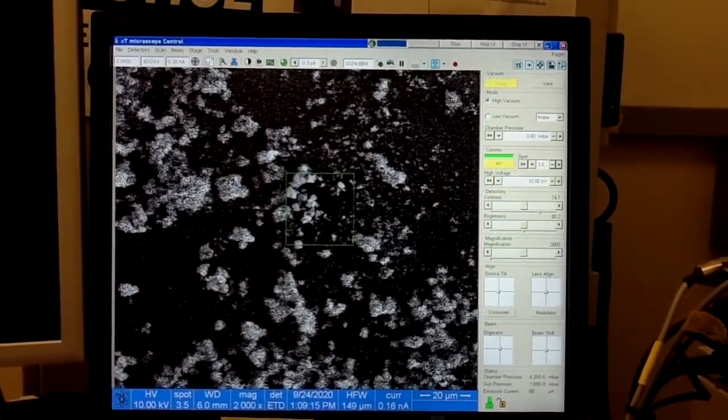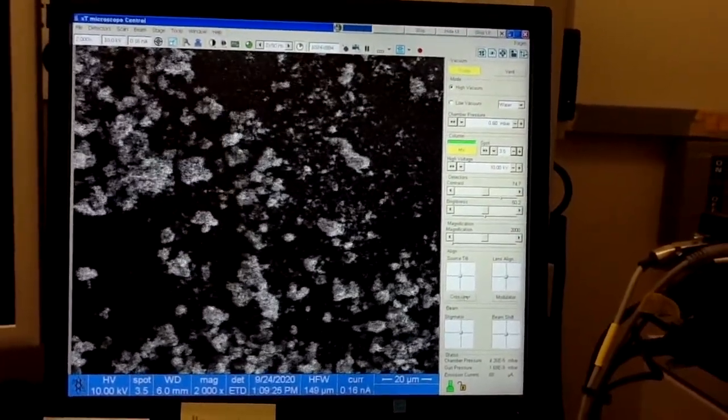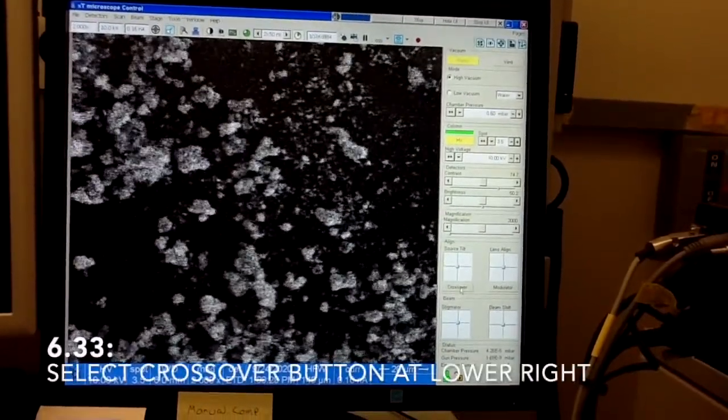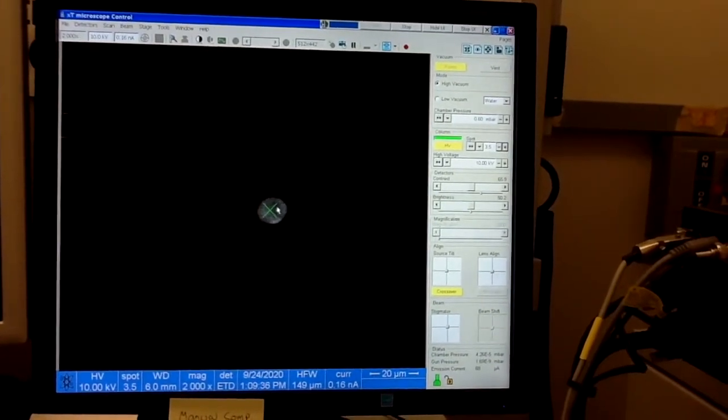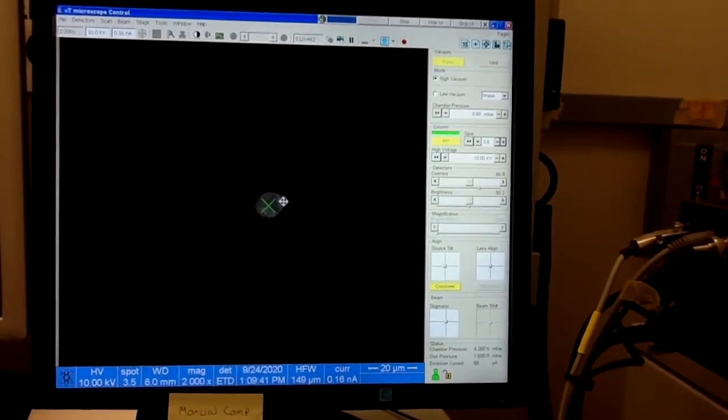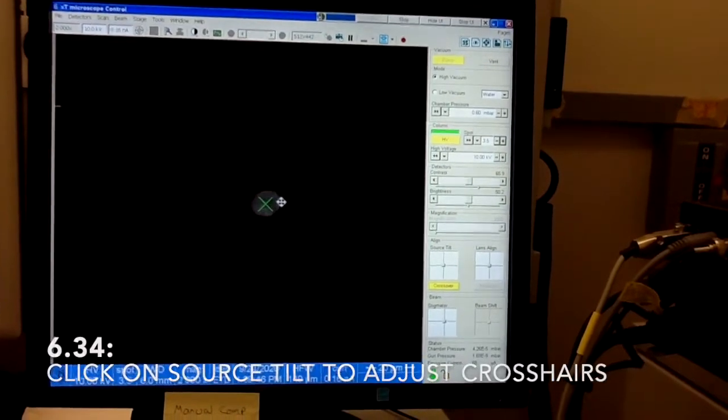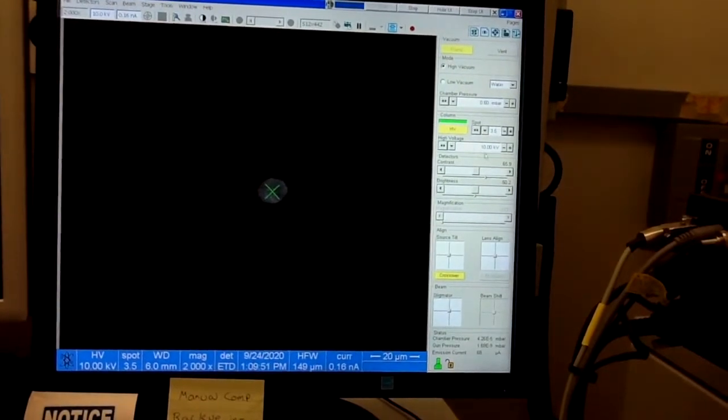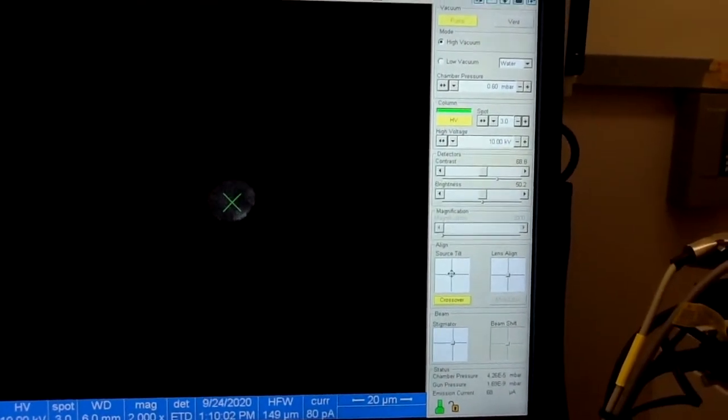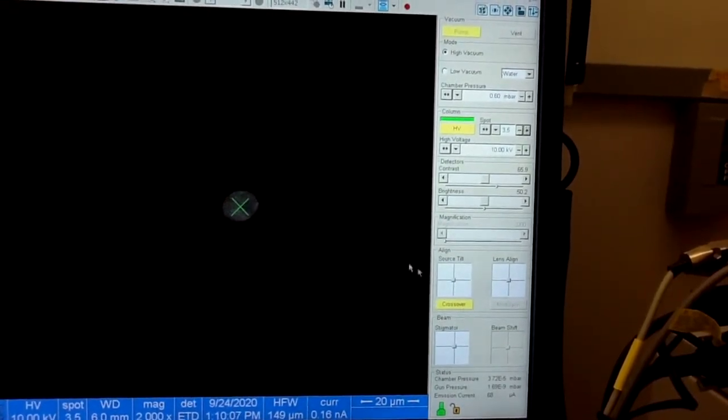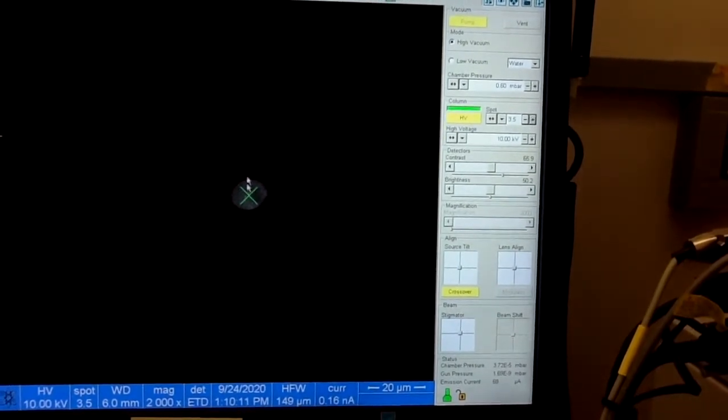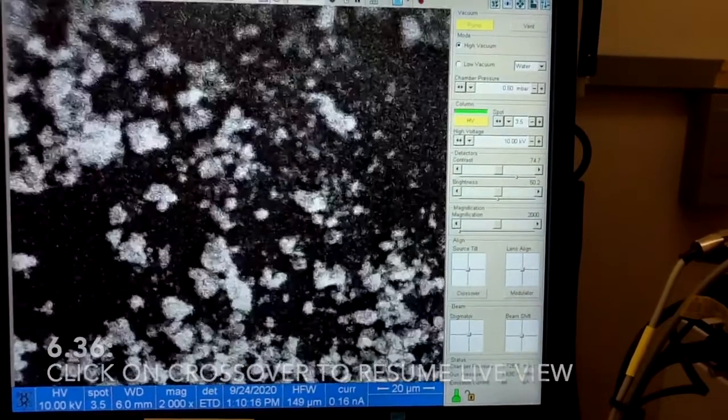One more thing which is important to know, if you have a low intensity of your beam, make sure that you check this crossover. Just click on the crossover button. You should see this bright disc and it should be centered around this cross. If it's too much off center you can just use this control and center it. And at every spot size and every voltage it will be in different locations. For example if we reduce the spot size to 3 you can see it's off center now so we need to correct. Now 3.5 should be as it is and then once you are good you, it looks center, just double click again crossover and you will go to the image.